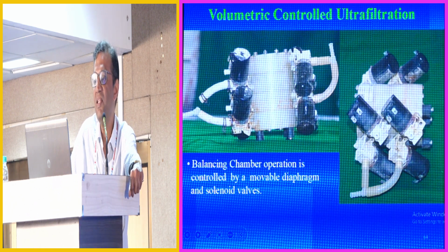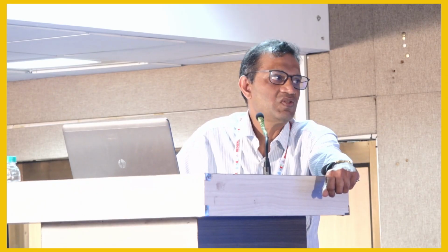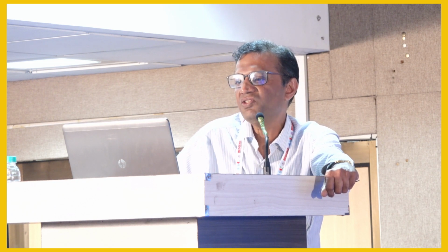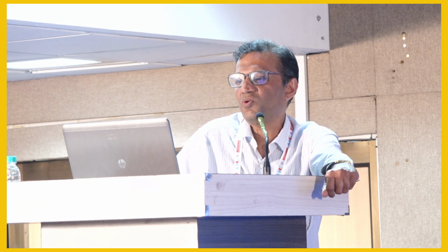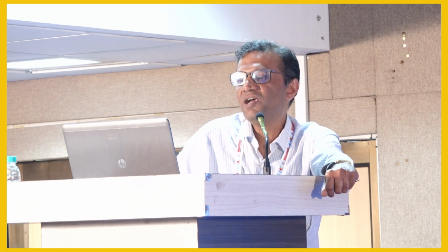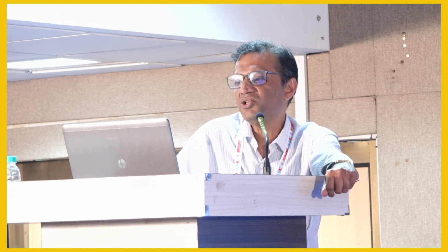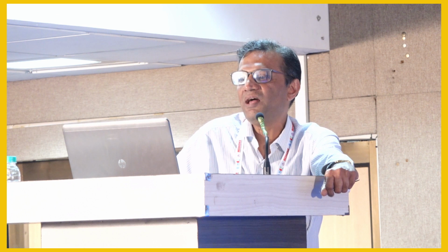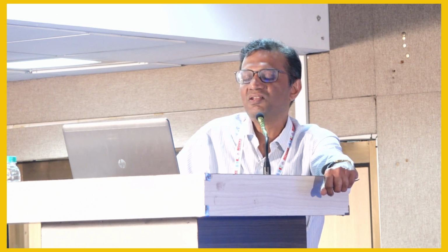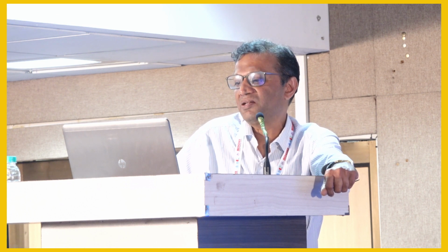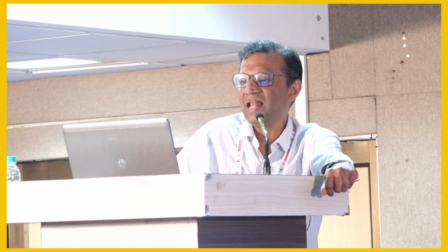This is what the balancing chamber of the Fresenius 4008 looks like. It has 8 valves, 4 on the inlet side and 4 on the outlet side, and the chamber is divided into 4 parts. There is a rigid partition here at the center, and there is a diaphragm which moves and divides each chamber into 2 parts. Now, this is what the diaphragm looks like. This is the Althin's UltraTouch system. The chamber is a bit bigger. It's 120 ml as opposed to 4008 where it's 30 ml.